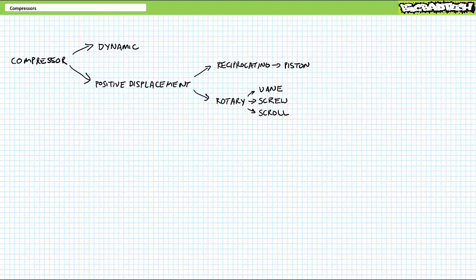Compressors are divided into two general families: dynamic and positive displacement. Dynamic compressors, like turbines or centrifugal compressors, are not within the scope of this particular lecture and we will limit our discussion to positive displacement compressors. Within the positive displacement branch, there are countless variations you might encounter in the field. However, the main types are reciprocating piston-style compressors and rotating vane and screw-type compressors.